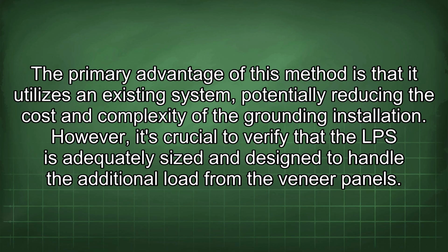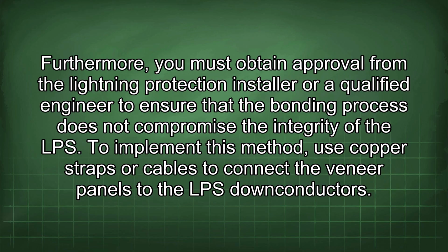The primary advantage of this method is that it utilizes an existing system, potentially reducing the cost and complexity of the grounding installation. However, it's crucial to verify that the LPS is adequately sized and designed to handle the additional load from the veneer panels. Furthermore, you must obtain approval from the lightning protection installer or a qualified engineer to ensure that the bonding process does not compromise the integrity of the LPS.